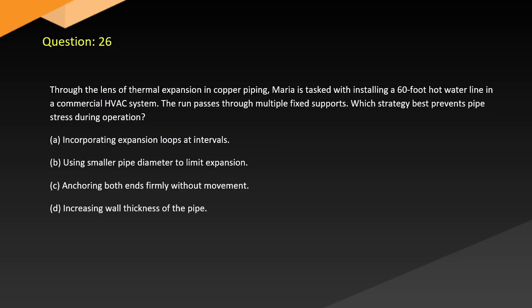Question 26. Through the lens of thermal expansion in copper piping, Maria is tasked with installing a 60-foot hot water line in a commercial HVAC system. The run passes through multiple fixed supports. Which strategy best prevents pipe stress during operation? A. Incorporating expansion loops at intervals. B. Using smaller pipe diameter to limit expansion. C. Anchoring both ends firmly without movement. D. Increasing wall thickness of the pipe.